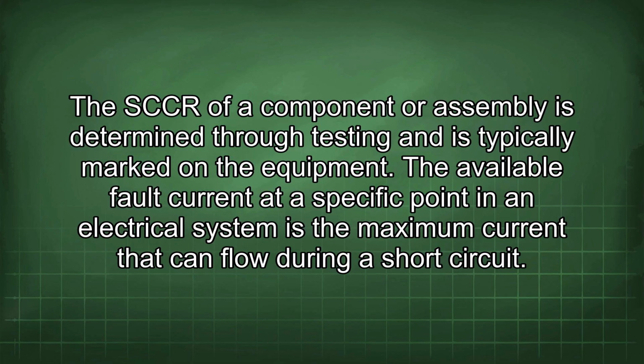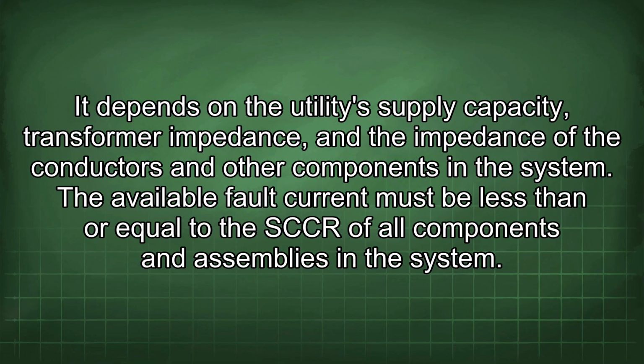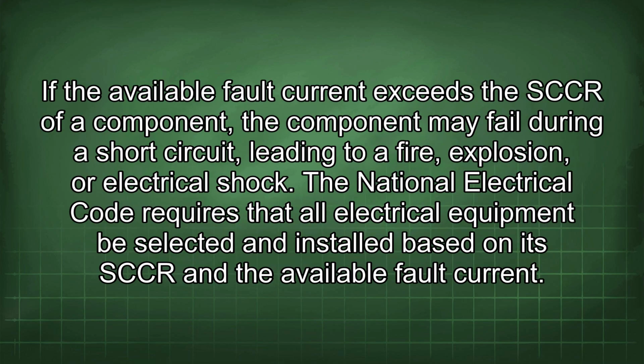The available fault current at a specific point in an electrical system is the maximum current that can flow during a short circuit. It depends on the utility supply capacity, transformer impedance, and the impedance of the conductors and other components in the system. The available fault current must be less than or equal to the SCCR of all components and assemblies in the system. If the available fault current exceeds the SCCR of a component, the component may fail during a short circuit, leading to a fire, explosion, or electrical shock.